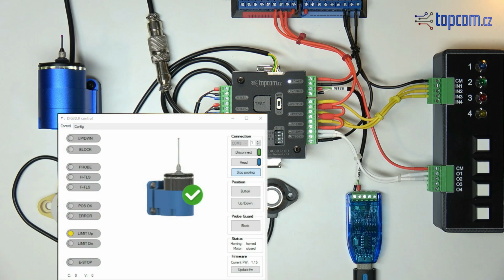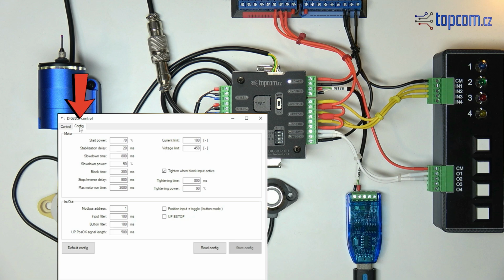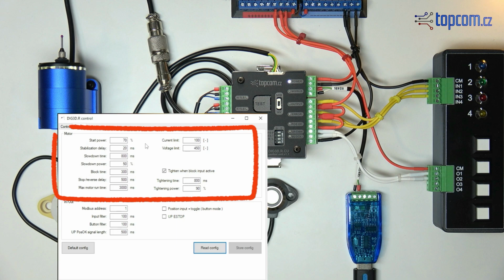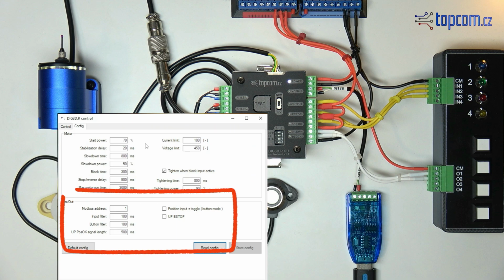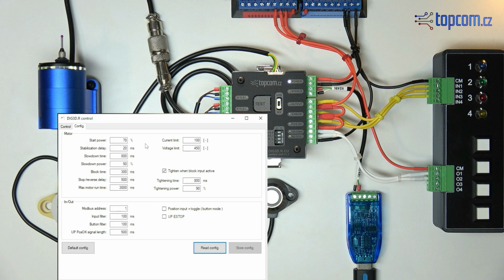Now let's briefly look at the configuration options available for the probe control unit. The configuration settings can be found under the Config tab in the application. Current parameters can be loaded using the Read Config button. The motor section contains parameters related to the probe's rotation process. The in and out section includes settings that define the behavior and function of the inputs and outputs.